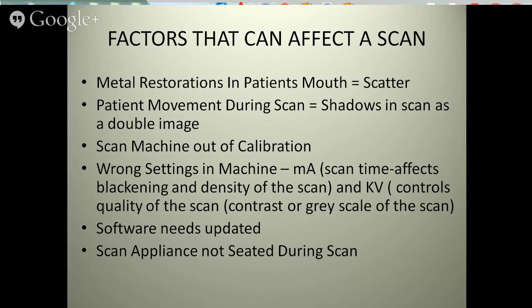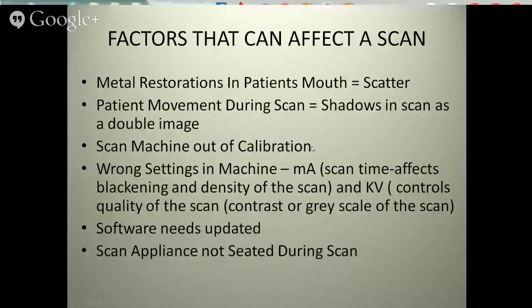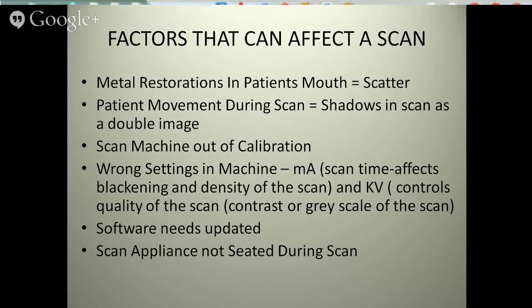If they ask you to get them another scan - however all of you operate with different companies that use this - all the machines have a calibration that they should meet, and they probably told you when you bought your machine how often these machines should be calibrated. Your rep should be able to come in and do that, or somebody from the company should be able to come in and do that. My suggestion is to have that done periodically and documented.